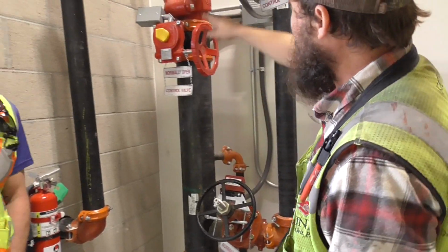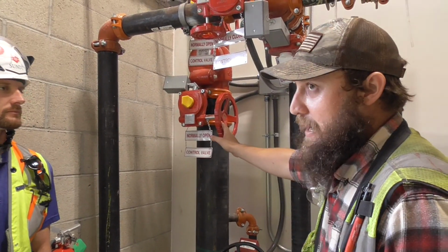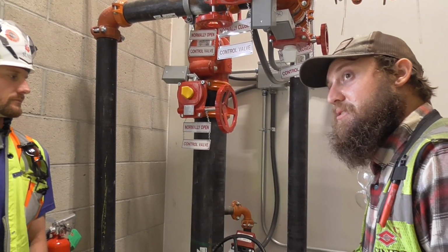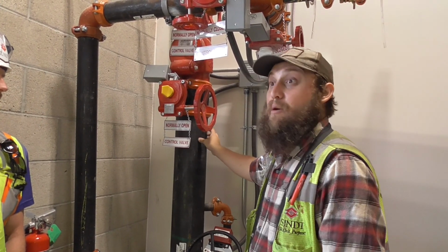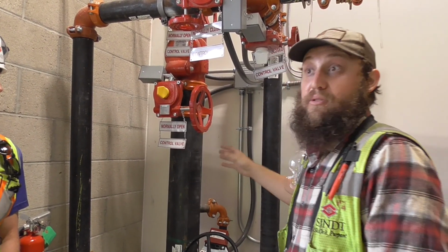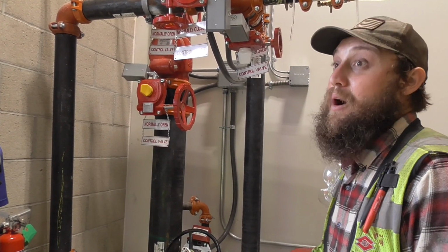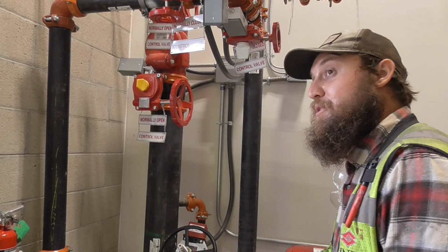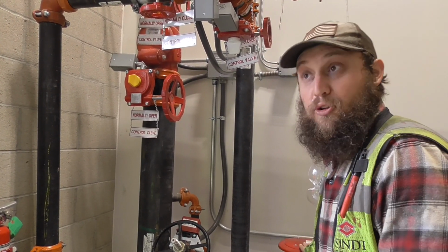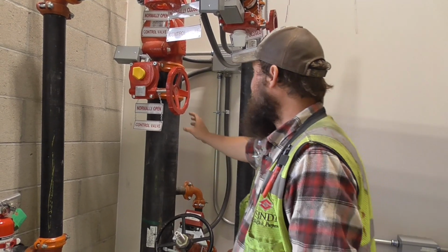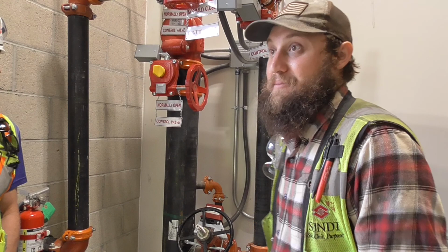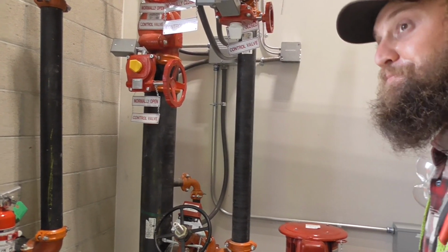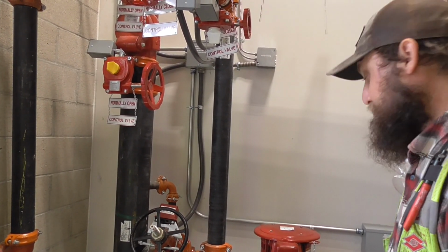This just feeds the bypass. So the point of the bypass is in case your pump fails, you want a larger diameter pipe for your bypass to allow maximum water pressure. So everything's designed to have the pump back it up. But for whatever reason, your main power fails, your alternate power fails, at least you have a larger than required diameter pipe to feed everything. That's why they have that, just as a precaution.